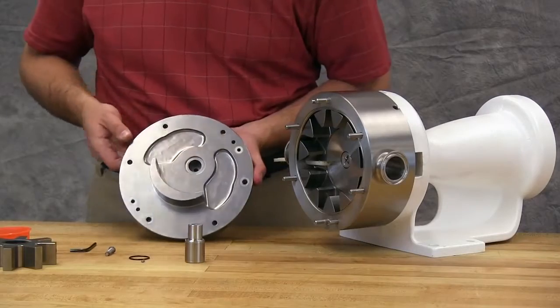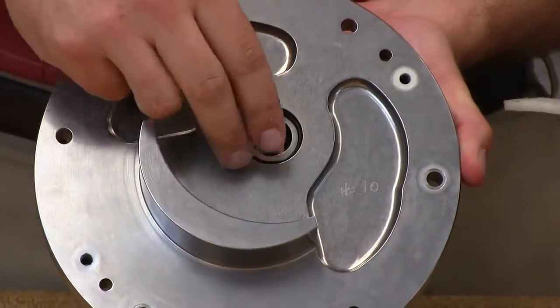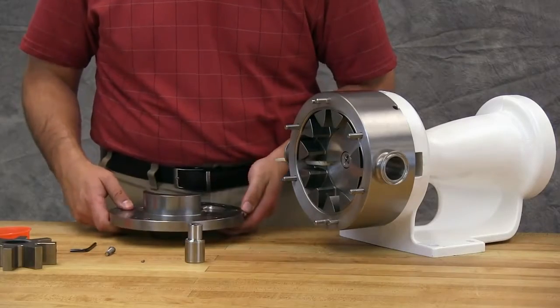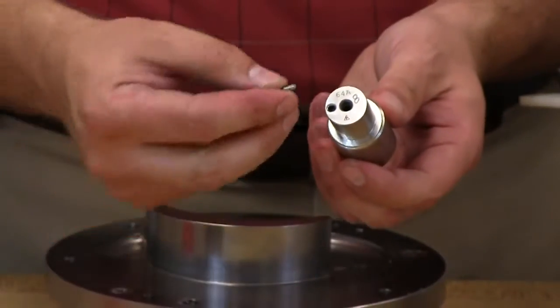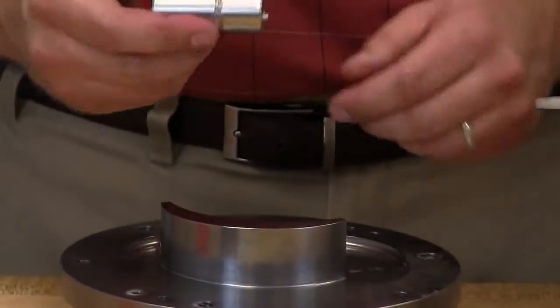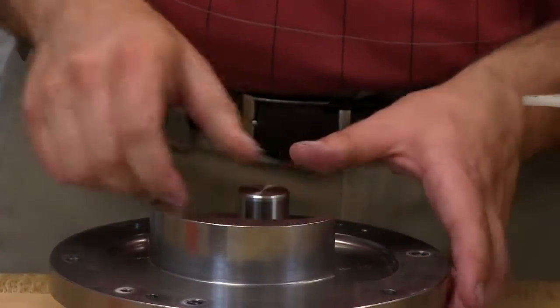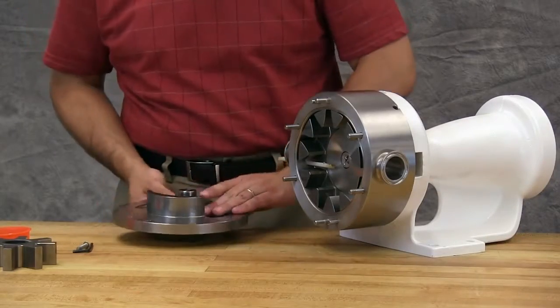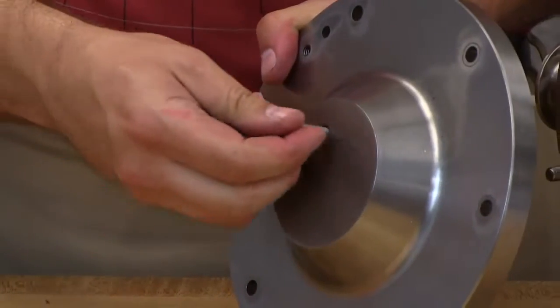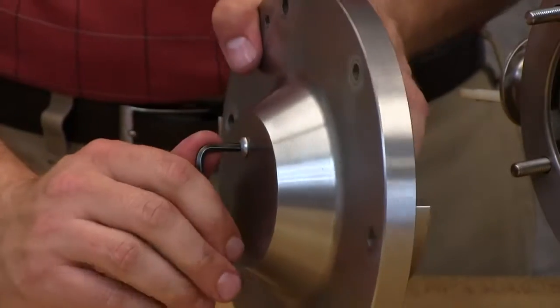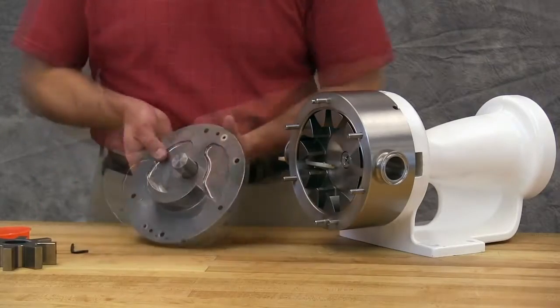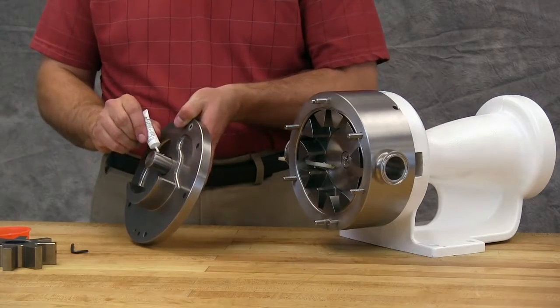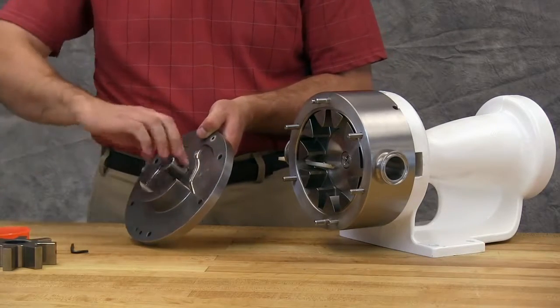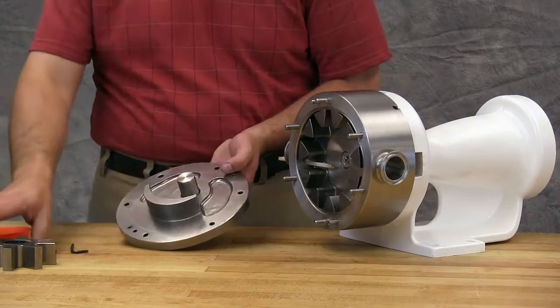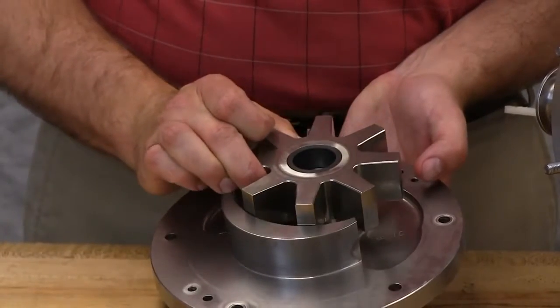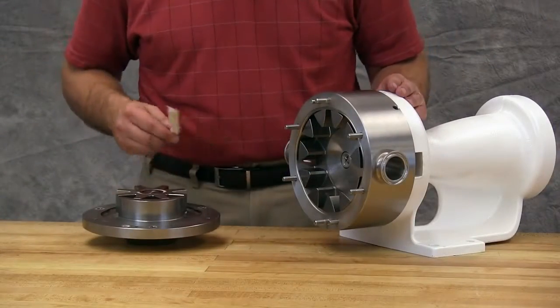If the idler pin was removed from the head, place the idler pin O-ring into the counterbore on the head. Insert the dowel pin into the idler pin. Align the dowel pin with the hole or groove in the bore for the idler pin and install the idler pin into the head. Secure the idler pin to the head using the idler pin cap screw. Coat the idler pin with a food-grade lubricant and place the idler assembly on the idler pin. Remove the plastic bar from the port opening.